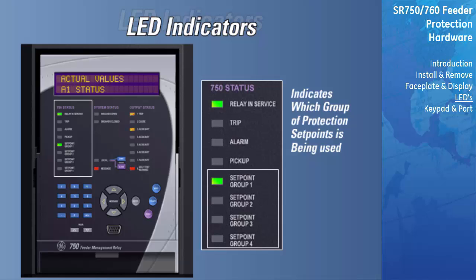If an LED is solid, this means that the indicated group is protecting. A setpoint group LED will flash when that setpoint group is being edited, but only if another setpoint group is being used to protect the system. For example, if setpoint group 1 is the active or protecting setpoint group, but the setpoints under setpoint group 4 are being edited, the setpoint group 1 LED will be solid, and the setpoint group 4 LED will be flashing.